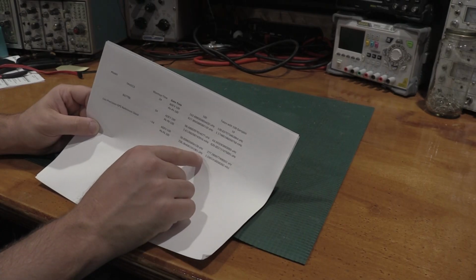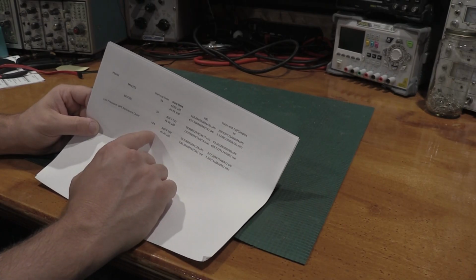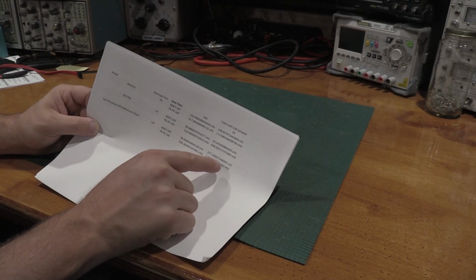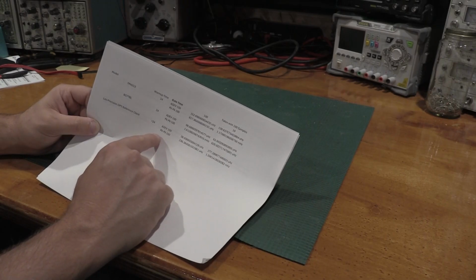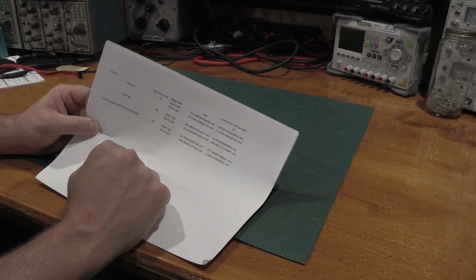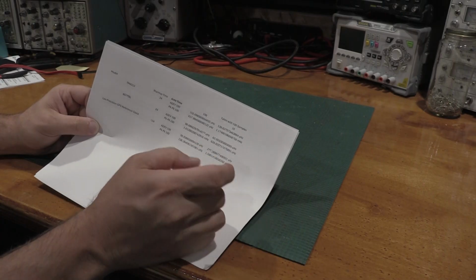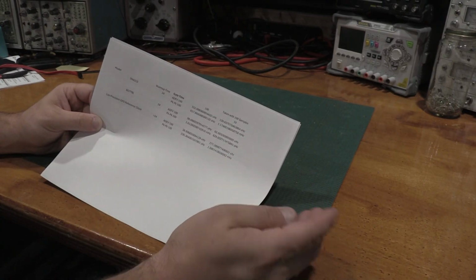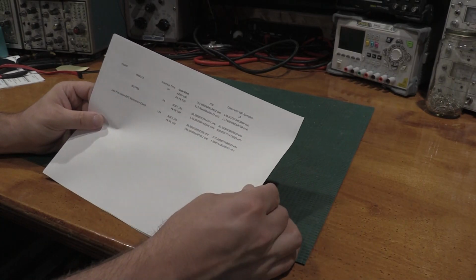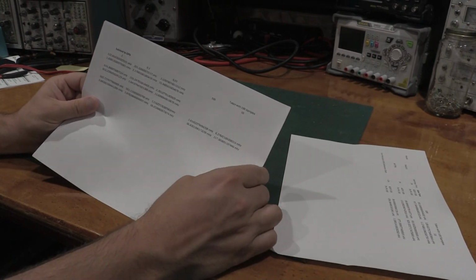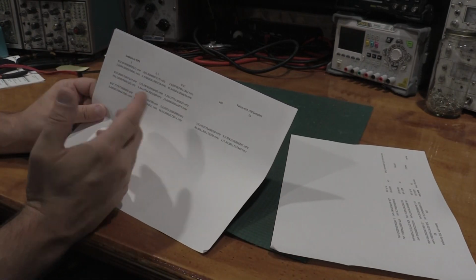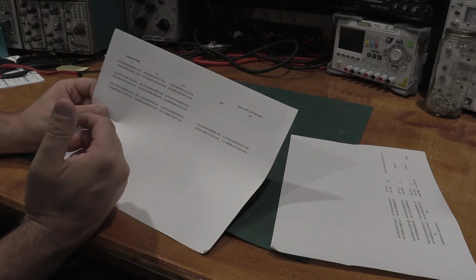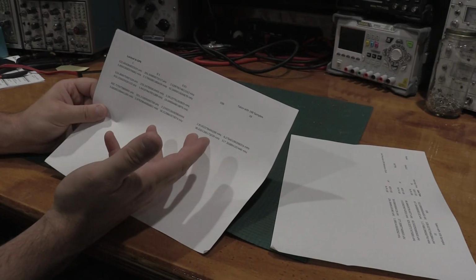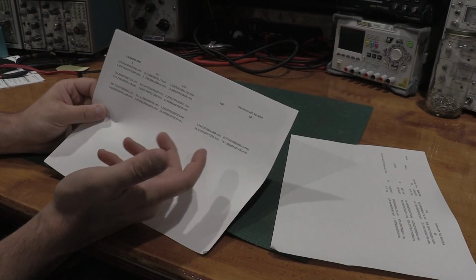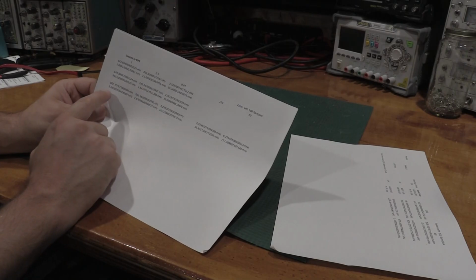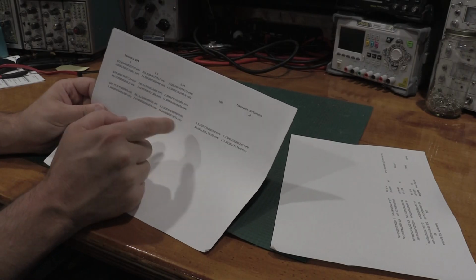With 10 seconds, we had an Allan variance of 277 microhertz and a peak-to-peak of 1 millihertz, or 1.5 millihertz. So we're still 3 orders of magnitude off of 1 hertz. So not bad, but not as stable as the fixed clocks. The fixed clocks get you a little bit more stability.